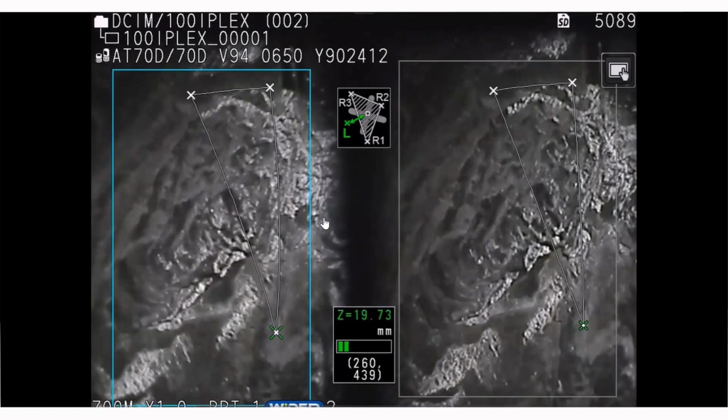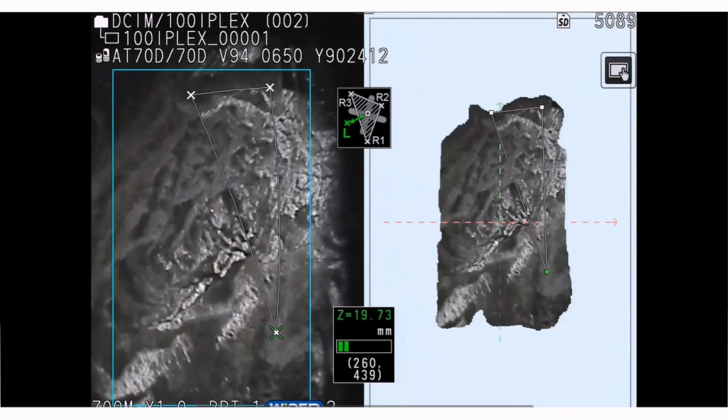In this case, I have already selected my reference points. This is the depth method. So I have 3 points, and the next one will be the measurement. I can see I am within the recommended measuring range, which is good. But what you see here is that it's very difficult to select what is the deepest point. It's difficult to see that just with the optical image. And that's where the 3D modeling plays a role.